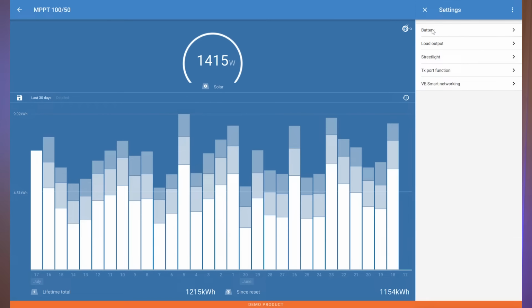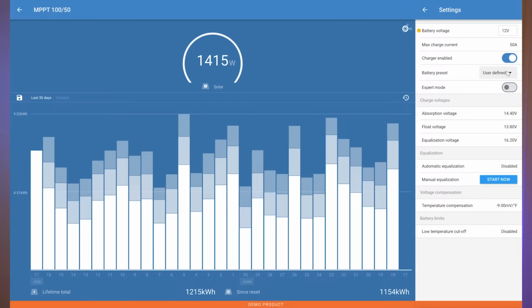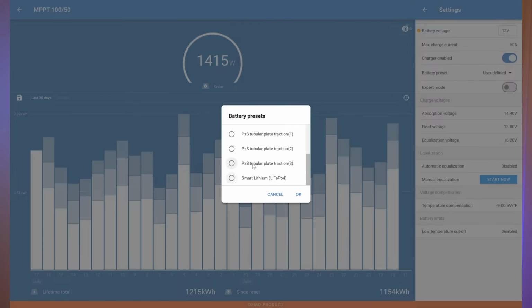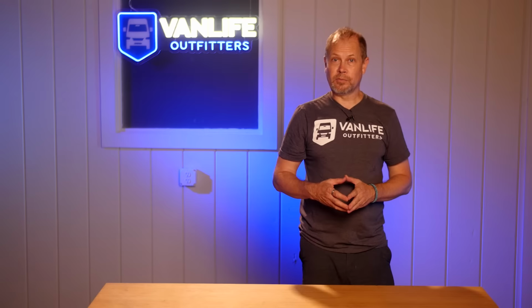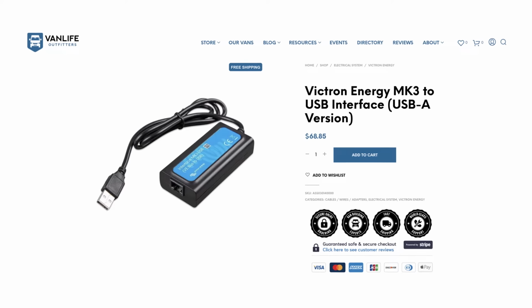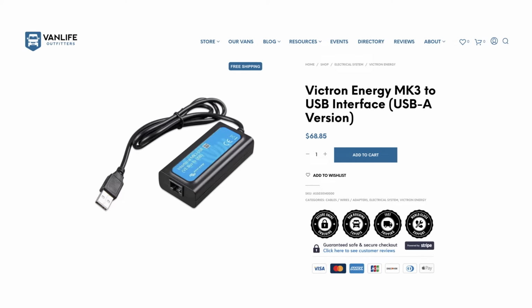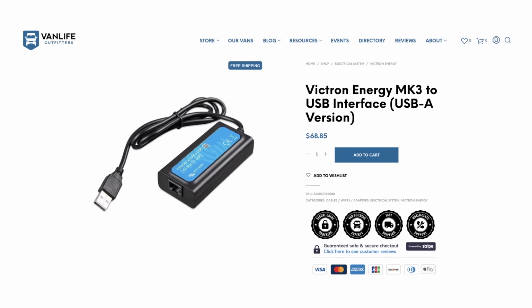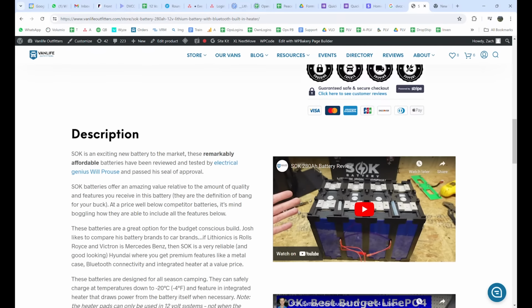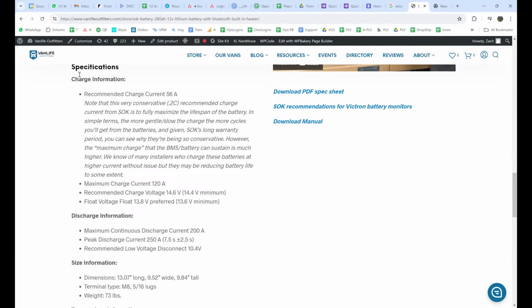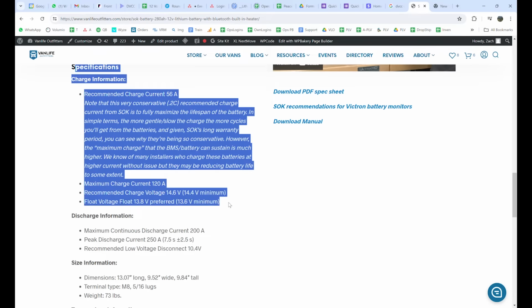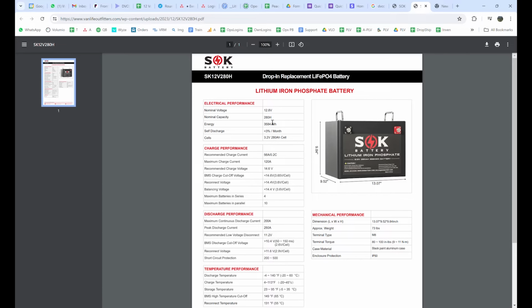Without DVCC, you would configure the charge profile in the settings of all of your chargers after wiring up the system. With Victron gear, this is typically done through Bluetooth with the Victron Connect app or with an MK3 to USB adapter for inverter chargers. So you'd find the specifications from the battery manufacturer and configure things like the absorption voltage, the absorption time, float voltage, etc. and so on.